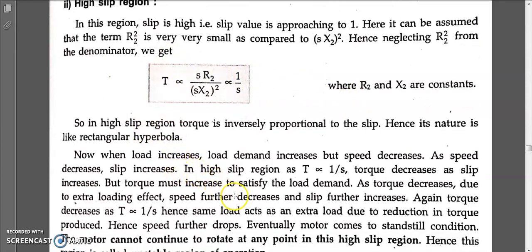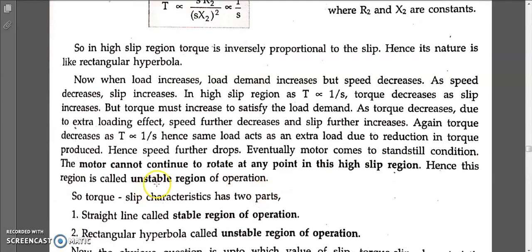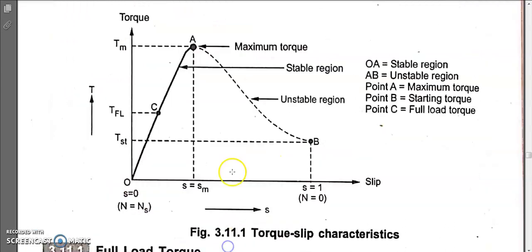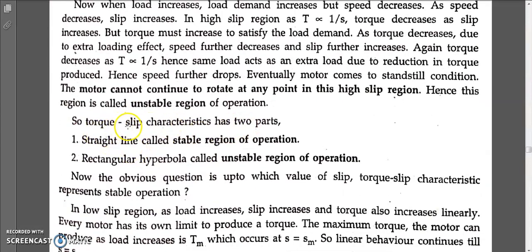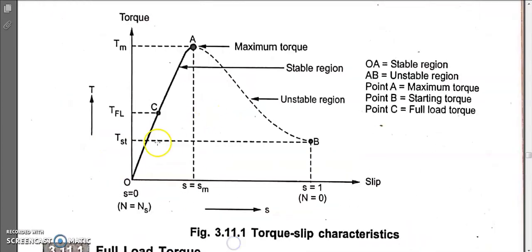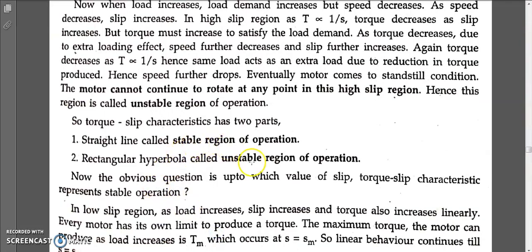As torque decreases, speed again decreases, which causes slip to increase further, which causes torque to decrease further. This cycle continues until the motor stops. So we cannot operate the motor in this region. If we operate above point A, the motor will eventually come to a standstill — speed will keep decreasing.